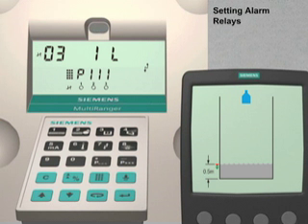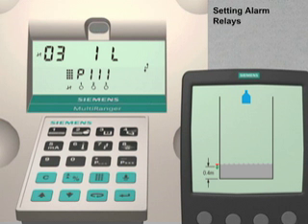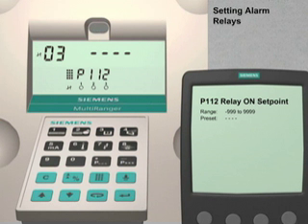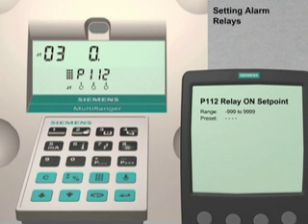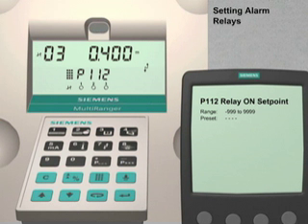The alarm set point values are stored in parameters 112 and 113. We will enter the on set point value first. Press the next display key. P dash dash dash is visible on the Multiranger display. Enter 112. The parameter 112 setting for relay number 3 is currently a null value as indicated by four dashes in the parameter index field. Enter 0.4 followed by the enter key to set the on set point value to 0.4 meters.